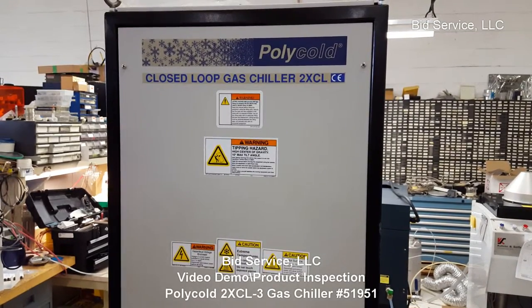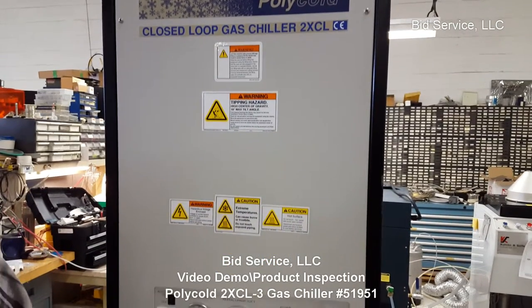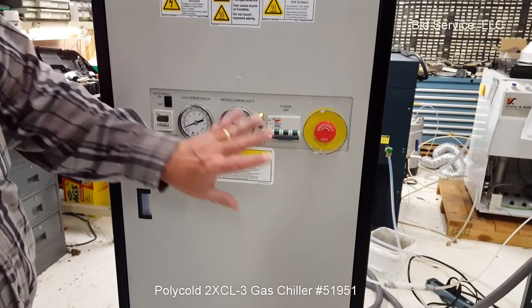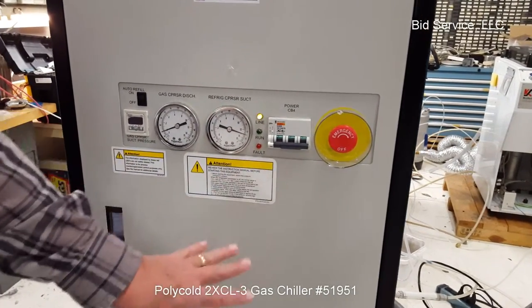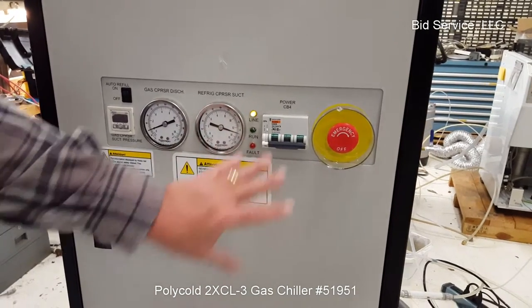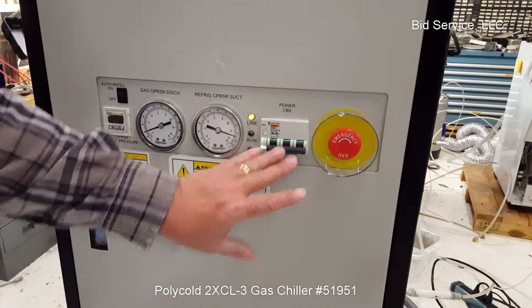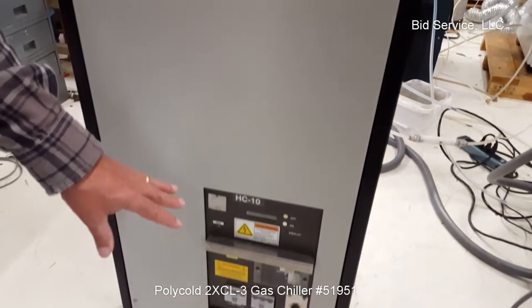This is a Polycold closed-loop gas chiller, 2XCL. All the controls are on the front. There's an emergency shut-off here. This unit has three circuit breakers for the different systems, and there are two different systems accessible from the front. The closed-loop refrigeration part is up here, and the main condenser unit and system is down there.